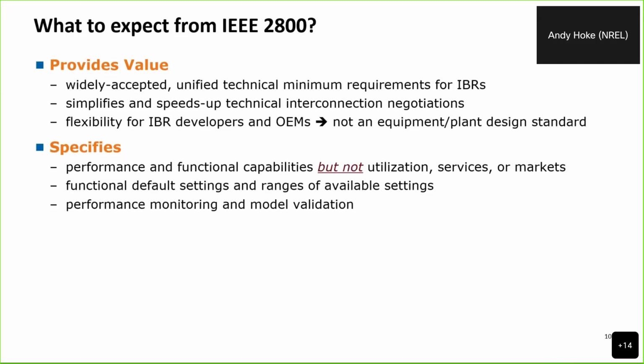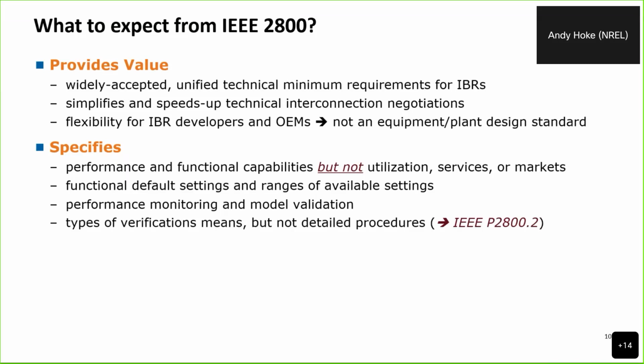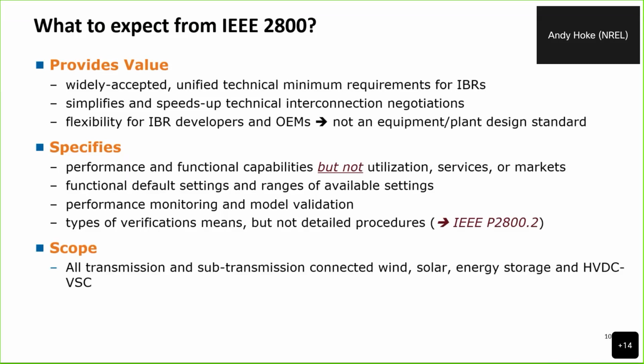It provides specific requirements on those types of settings for plants, which is shown to be crucial for diagnosis of events that have happened in the field. It also provides some information on data needed to validate that models of the plants are valid. It also provides an outline of a process for verification of the requirements that it outlines, but it doesn't provide the detailed procedures for those verification steps. That would occur in IEEE 2800.2.